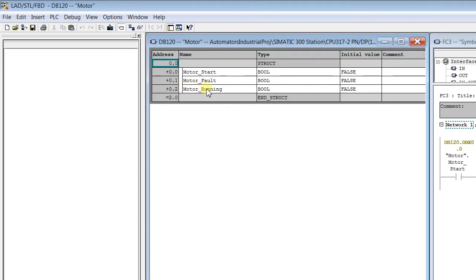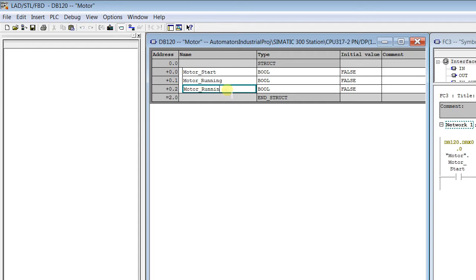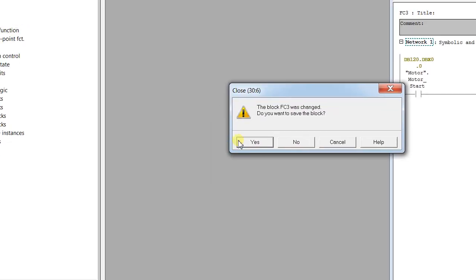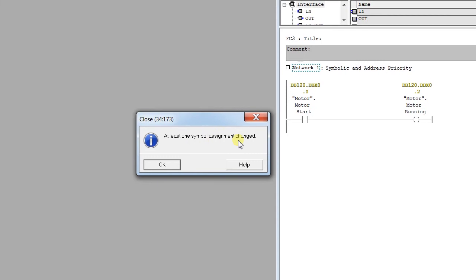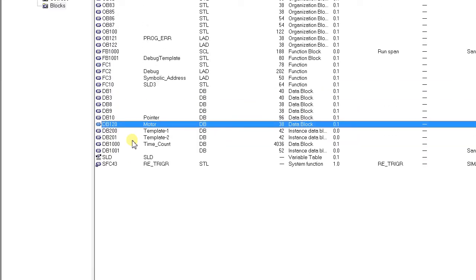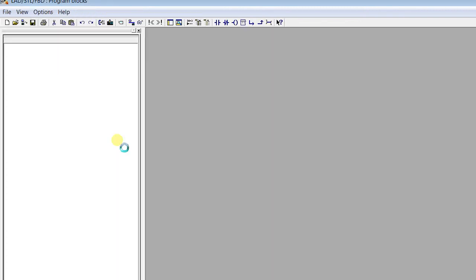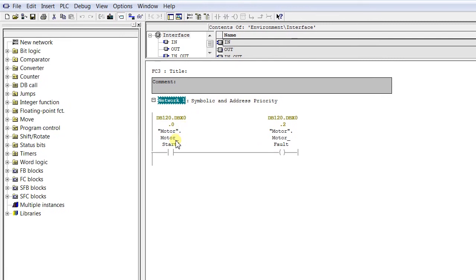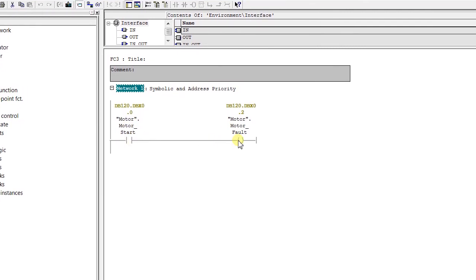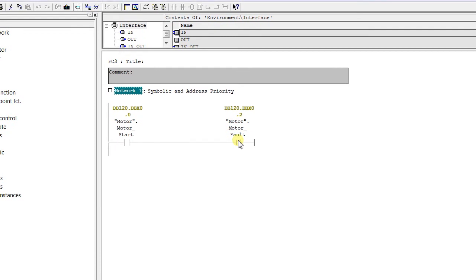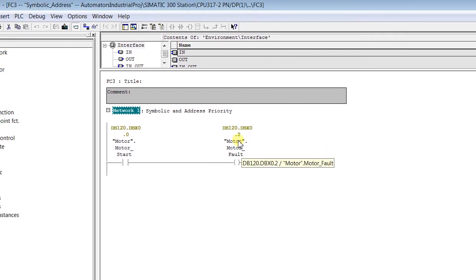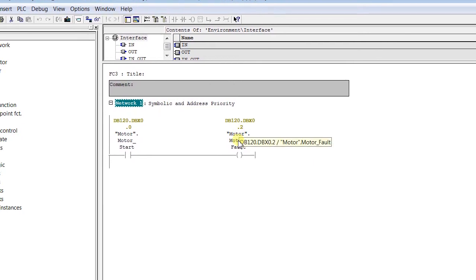I have shuffled the symbol assignments — you can see the message 'at least one symbol assignment is changed.' Opening the program again, at the beginning the network had Motor Start as the input and Motor Running as the output coil. After changing the symbol, the address is still the same.